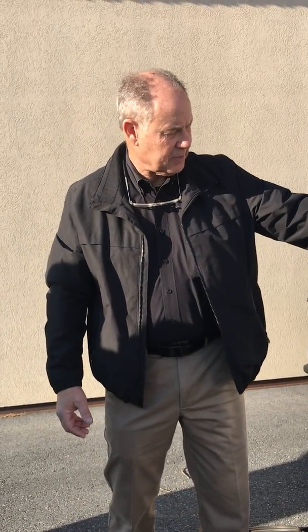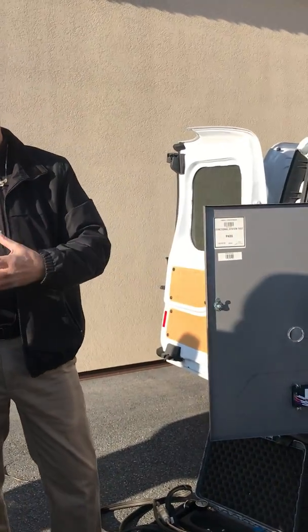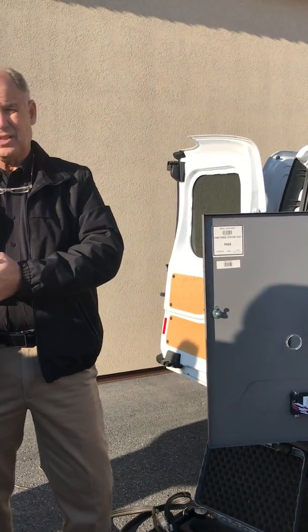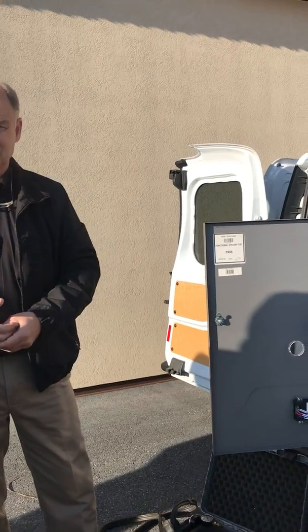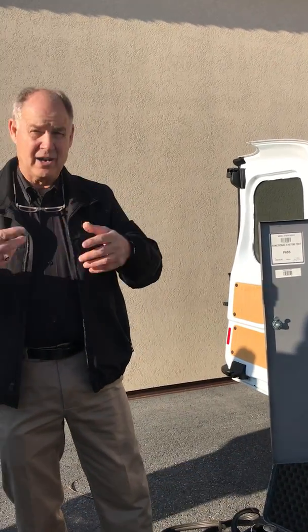So they have frost protection built into this. If the temperature of the heat exchanger gets too cold, it will turn on the circulator, and if it doesn't rise, it turns on the burner. So it fires even if there's no call for heat. So it gives you freeze protection.